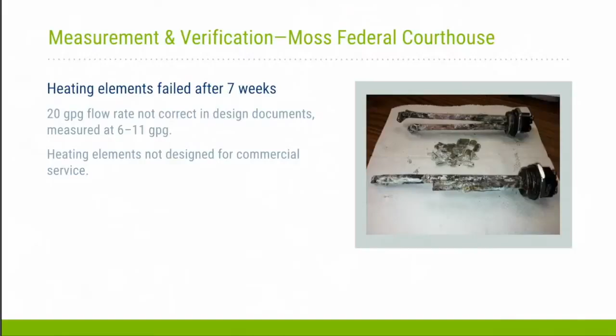what we found was that the original drawings, which we used to find out how much water was flowing through the pipe, the recirculating line, said that there were 20 gallons per minute flowing through that line. We actually put a flow meter on the line, an ultrasonic flow meter, and we found that the flow varied only between 6 and 11 gallons per minute, not 20 gallons per minute.